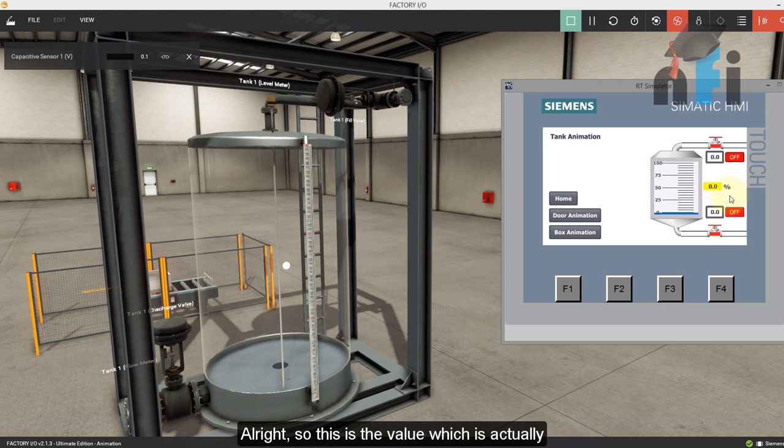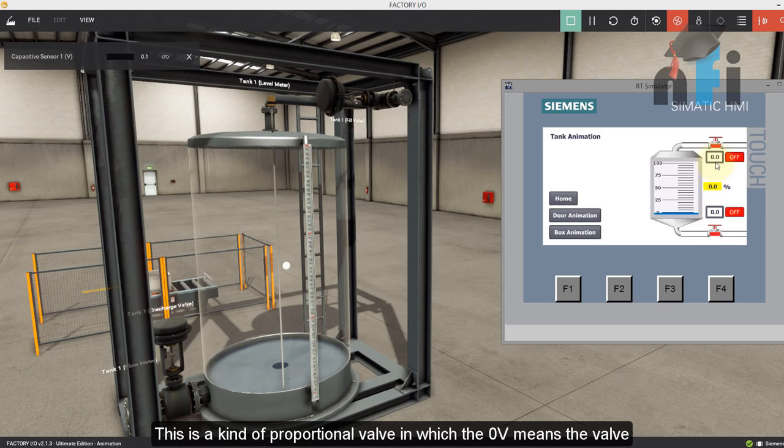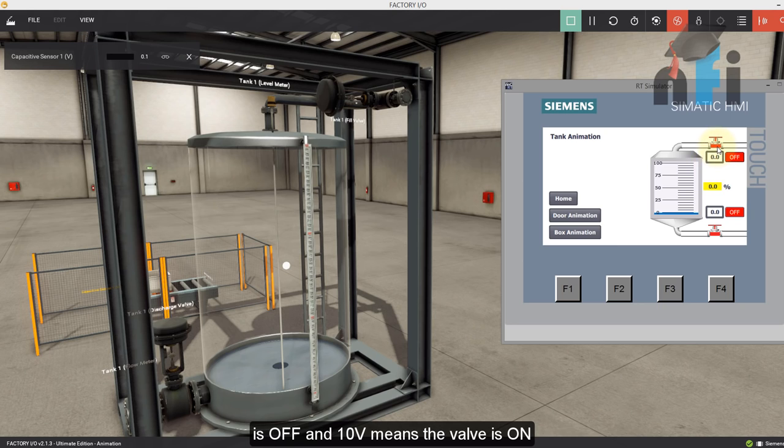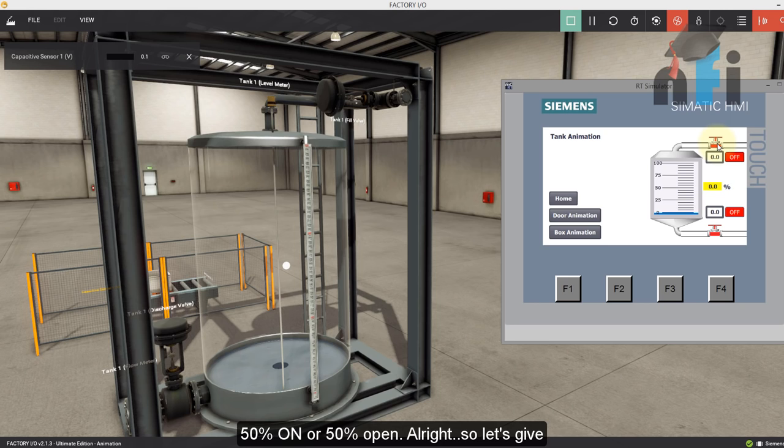So this is the value, which is actually the voltage, which we are giving to the valve for on and off operation. So this is a kind of proportional valve in which the zero volt means the valve is off, the 10 volt means the valve is on, which is 100% on. And if I give five volt, this valve is 50% on, or 50% open.